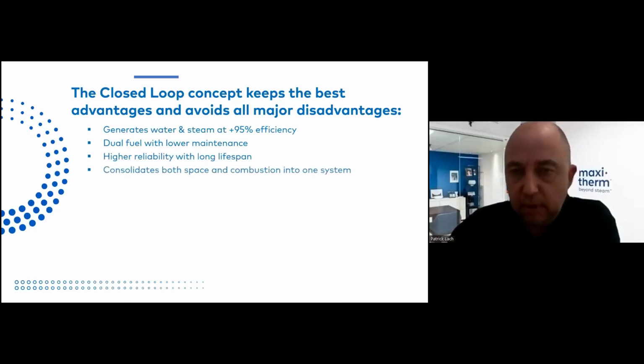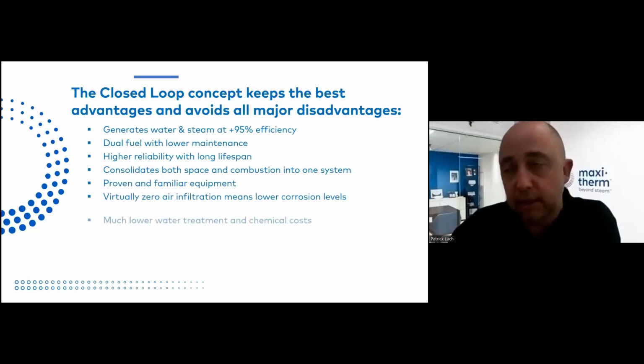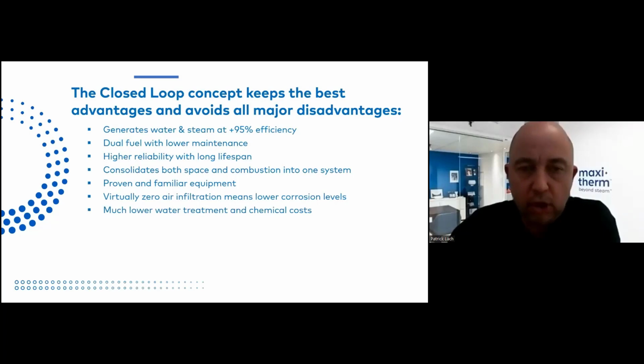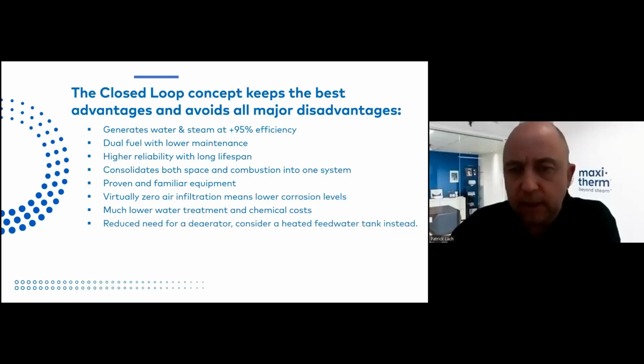Consolidate both space and combustion into one system. Proven and familiar equipment, no doubt about it. Virtually zero air infiltration means lower corrosion levels. We'll discuss that, and actually, I discussed this in the other YouTube video. Much lower water treatment and chemical costs, big time. Reduced need for a deaerator, consider a heated feed tank instead. Blowdown below 1%.